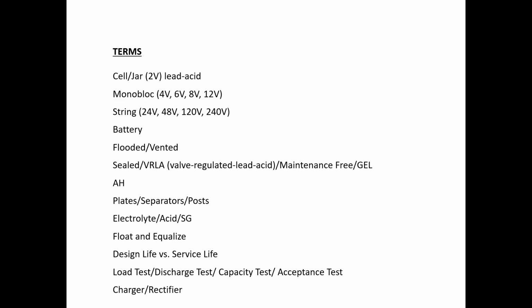Design life versus service life is actually pretty interesting. The design life of a battery is, if that battery dies of natural causes, grid corrosion, things that just happen in the normal life of a battery in service, they design around that. So they'll design grid thickness, amount of electrolyte, the paste. It's all designed with the idea that valve-regulated batteries are typically either a 10-year design life or a 20-year design life. A 10-year design life is usually that monoblock car-style battery. So that's what it's designed for, in a perfect world, how long it should last.